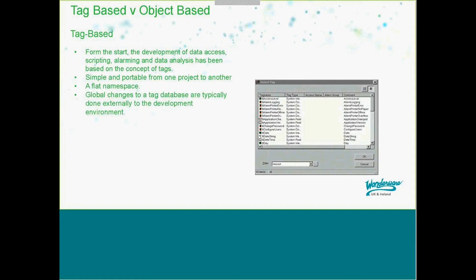Global changes to a tag database are typically done externally to the development environment — using external tools like a text file editor or Microsoft Excel, and then importing that back into your application. Reuse in a tag-based system is commonly set up through dynamic or client-server referencing. The system creates a common graphic containing scripts that switch the tags at runtime. Because the application structure is flat, the user needs to change each tag in the system and analyze how that change affects the rest of the application.